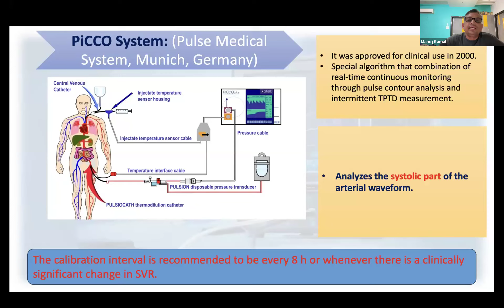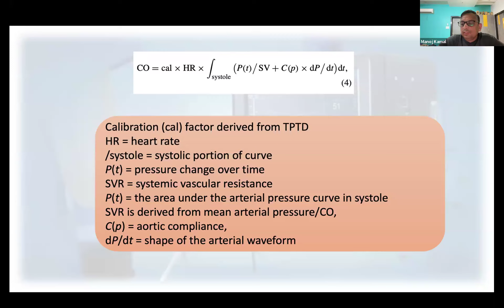For this monitor, the calibration interval is recommended to be every 8 hours or whenever there is a clinically significant change in SVR. This formula is used for the calculation of the cardiac output. In that, the systolic portion of a curve is undertaken, and there is the pressure change over time. dP/dt is the pressure change over time. SVR is systemic vascular resistance, and the integral is the area under the arterial pressure curve in systole, and C(p) is the aortic compliance. dP/dt is the shape of the arterial waveform. It can be measured by the shape of the arterial waveform.